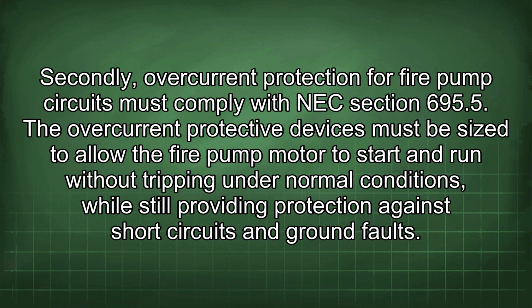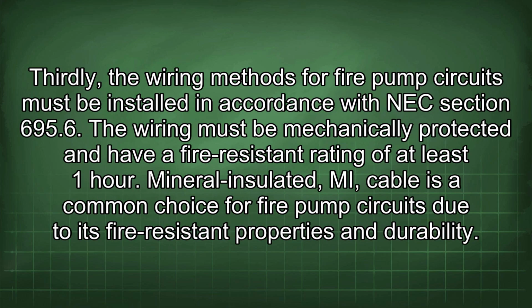Secondly, overcurrent protection for fire pump circuits must comply with NEC Section 695.5. The overcurrent protective devices must be sized to allow the fire pump motor to start and run without tripping under normal conditions, while still providing protection against short circuits and ground faults. Thirdly, the wiring methods for fire pump circuits must be installed in accordance with NEC Section 695.6. The wiring must be mechanically protected and have a fire-resistant rating of at least 1 hour. Mineral insulated cable is a common choice for fire pump circuits due to its fire-resistant properties and durability.